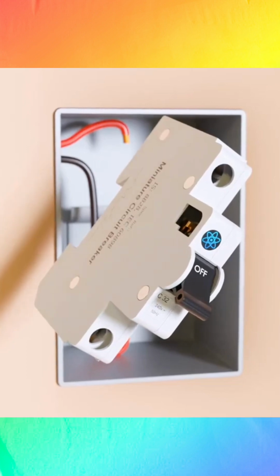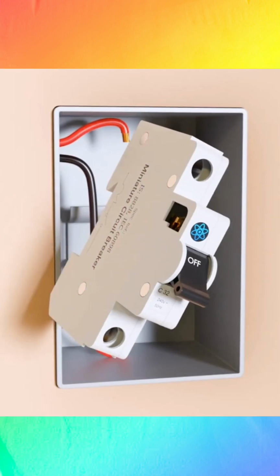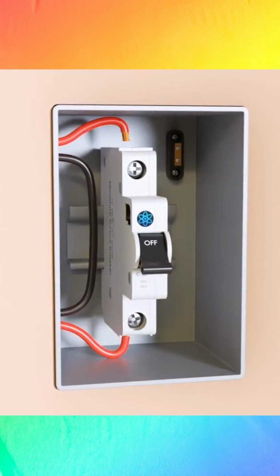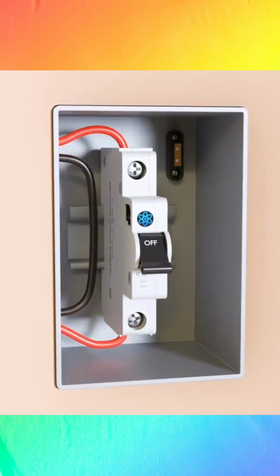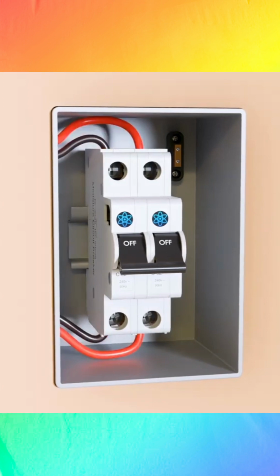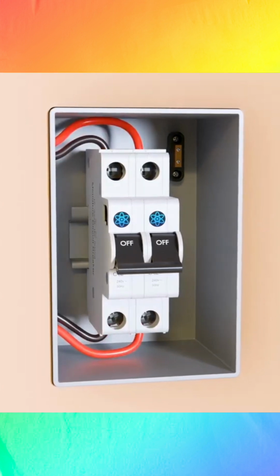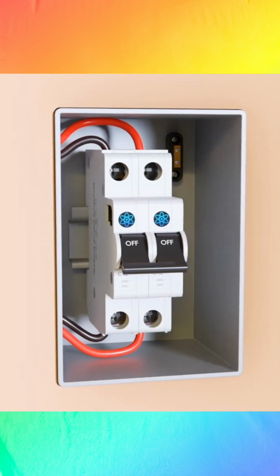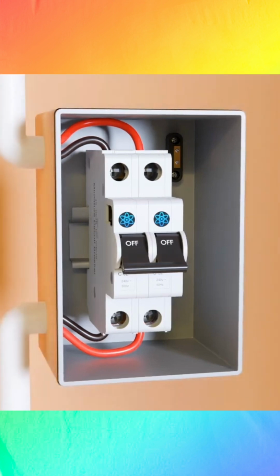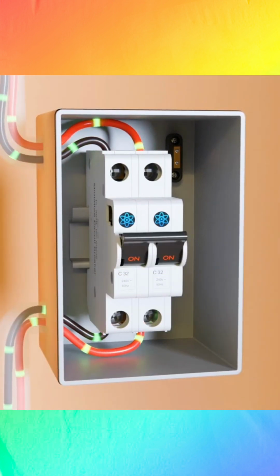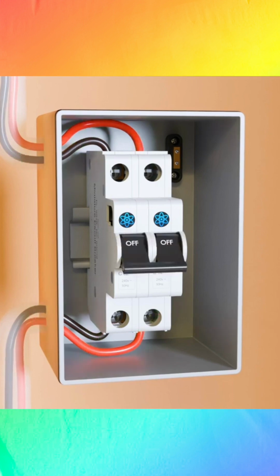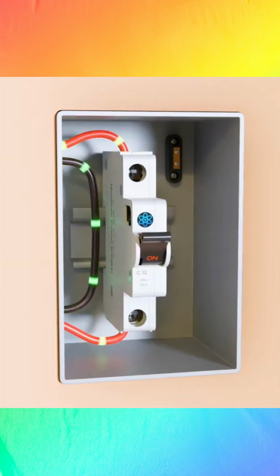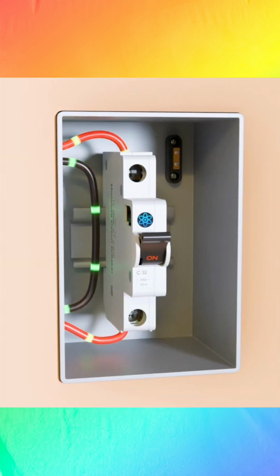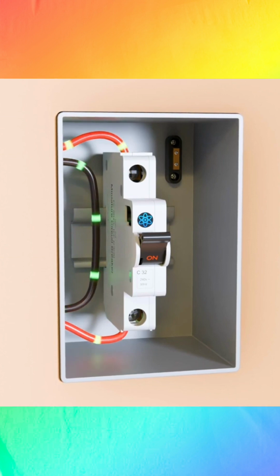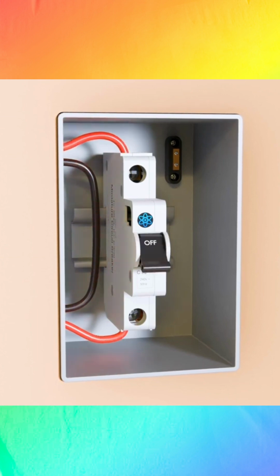Here comes the role of the miniature circuit breaker. Normally, a miniature circuit breaker is connected to the phase wire. However, in certain situations, a two-pole MCB is used instead of a single-pole MCB. This is done because a two-pole MCB offers an extra level of protection by also including the neutral wire. An MCB is a self-operated switch. It means when current rises above its recommended value, an MCB automatically trips and protects the system.